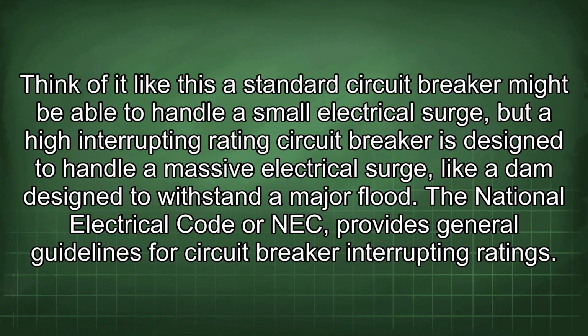Think of it like this: a standard circuit breaker might be able to handle a small electrical surge, but a high interrupting rating circuit breaker is designed to handle a massive electrical surge, like a dam designed to withstand a major flood. The National Electrical Code, or NEC, provides general guidelines for circuit breaker interrupting ratings.